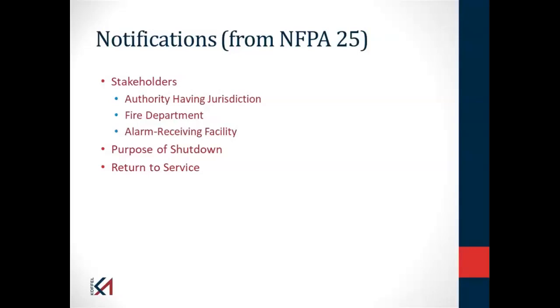If something happens tomorrow during a test, they'll just say it's part of the test, and without advance notice, no one will respond unless told to. So give advance notice to everybody that you're going to test the system. It's not uncommon for me to check into a hotel and get a notice that from 10 to 3 tomorrow they'll be testing the fire alarm system, so now I know a test is going on.